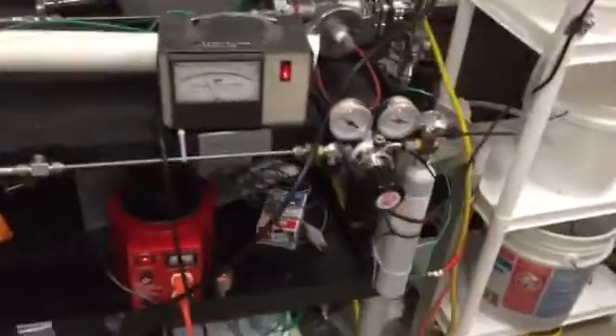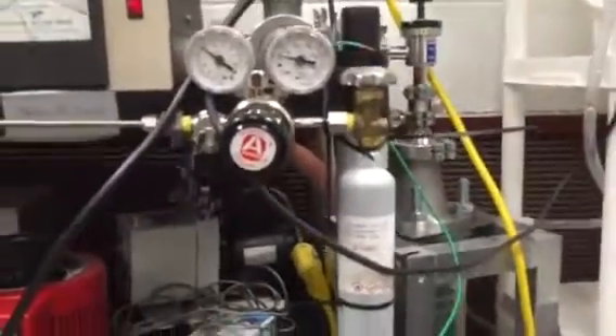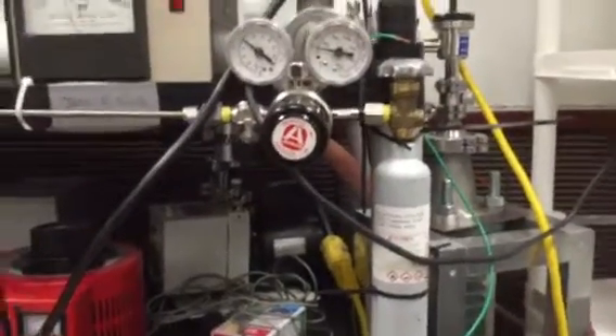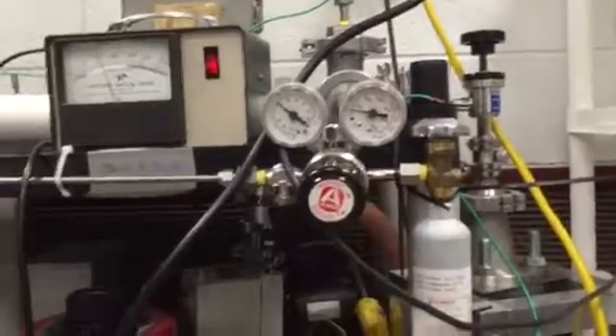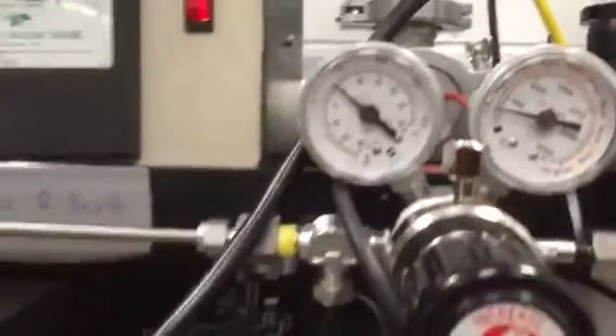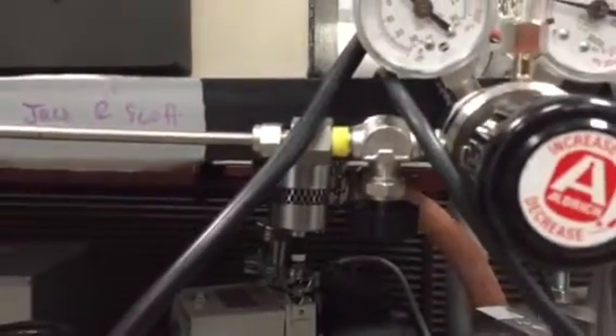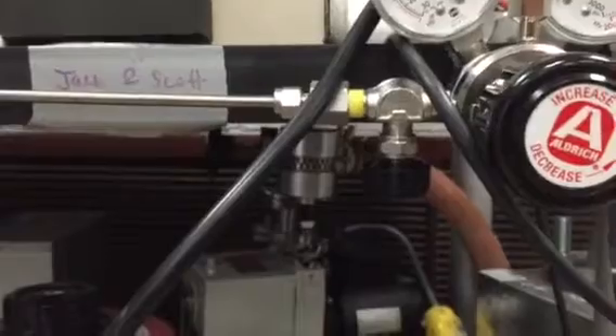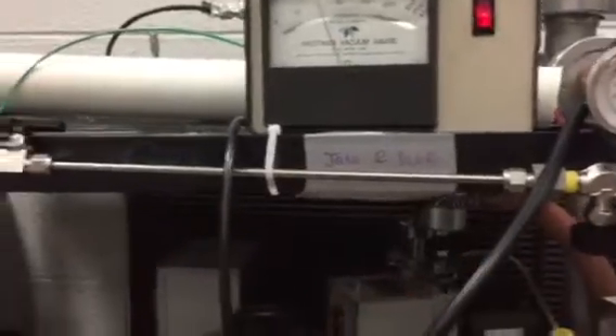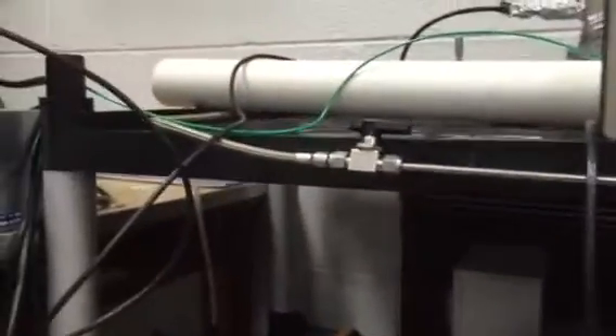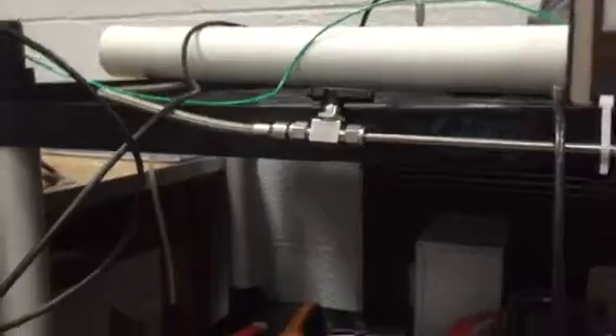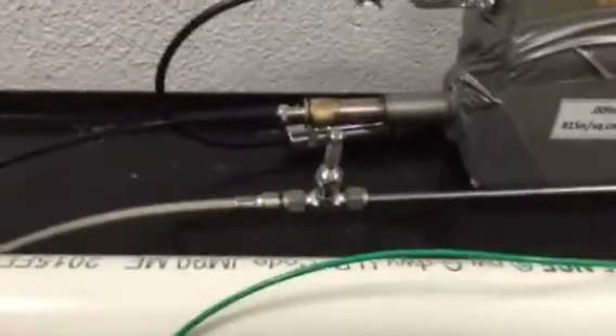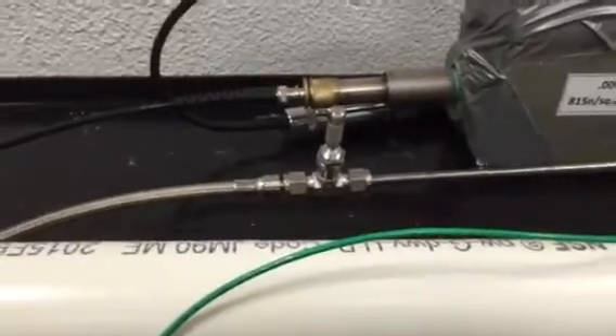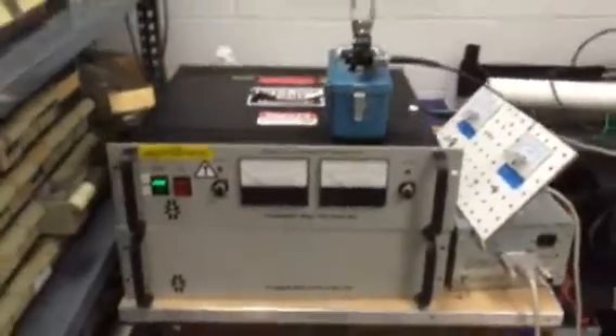Next, we have the deuterium gas system. For this, we have a 10-liter lecture bottle of 99.8% deuterium, which is then attached to a regulator which is adjustable from 0 to 30 psi. This then has a high flow needle valve, which we don't use for regulating the deuterium flow, but we do use it to fill up this short section of 1/4-inch stainless steel tubing, which we basically use as a reservoir during operation. Next, we have our Swagelok 1/4-inch shutoff valve, and then we have a Swagelok SS-SS4 needle valve. Next is our high voltage power supply.